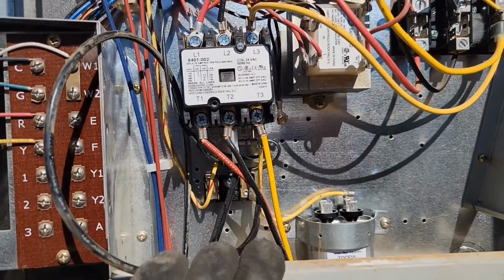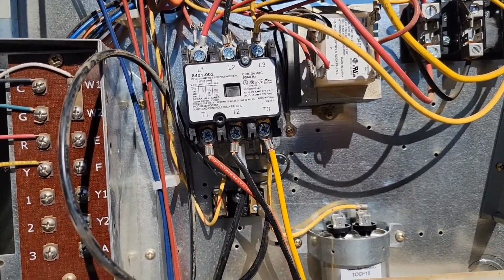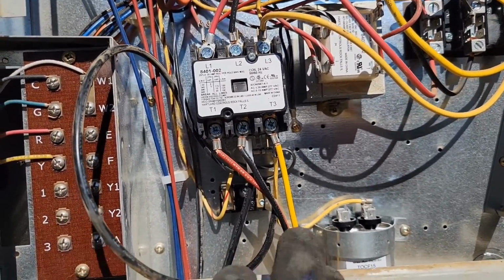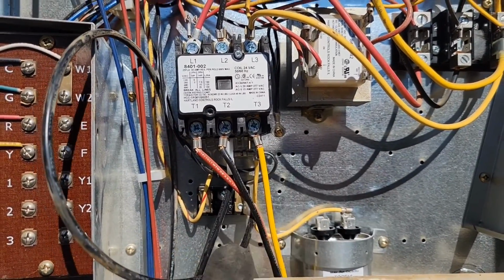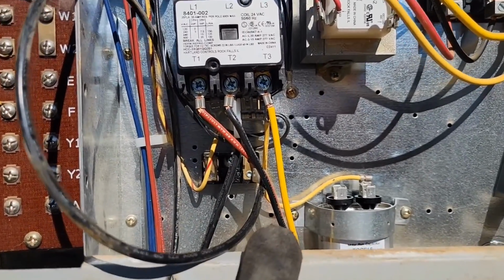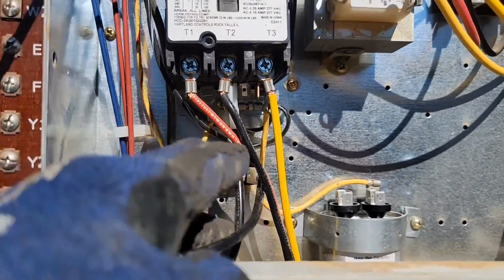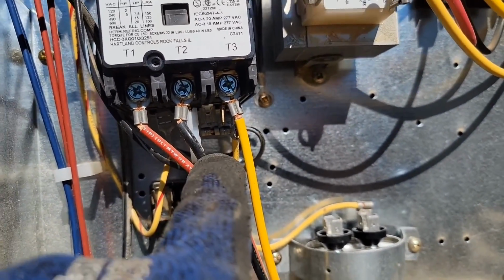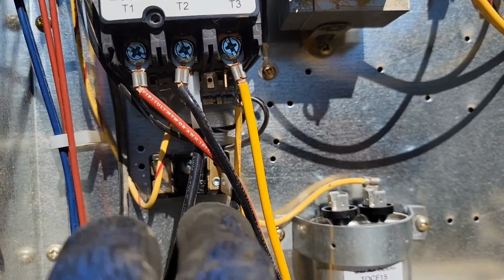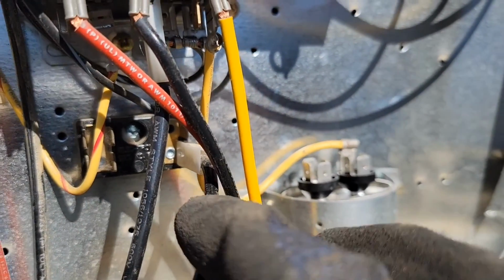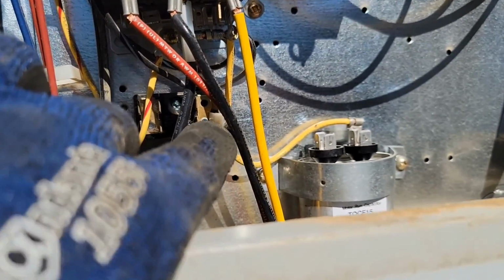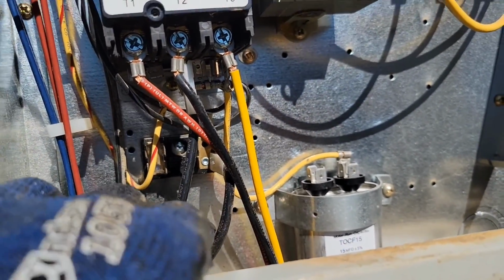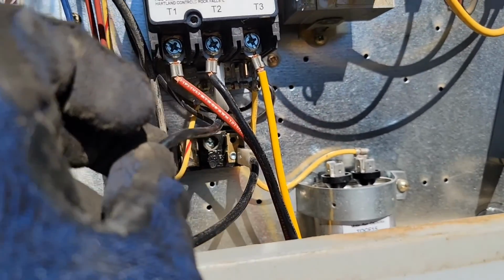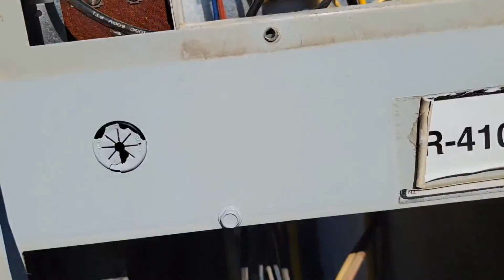So I'm gonna show you how I verified there was power, and I wanna talk about the pressure switch and how it's wired. So T2 and T3 is the power that goes to this outdoor fan motor. And you can see there's a black wire that comes from T2 terminal. See that right there? It's got that white spade. So we've got another black wire that has another spade, and our fan wire actually connects to this terminal, right? So the pressure switch is sent power from T2.